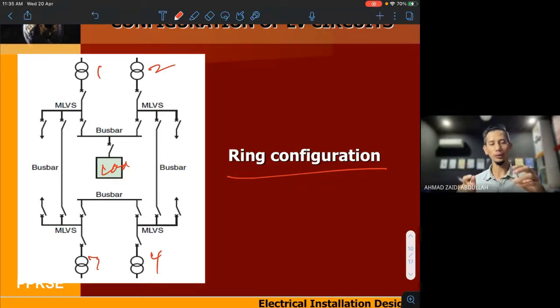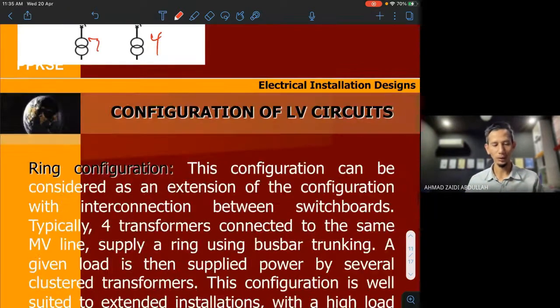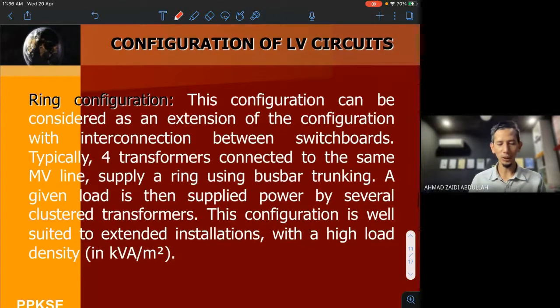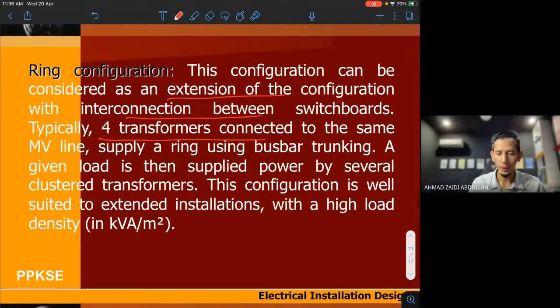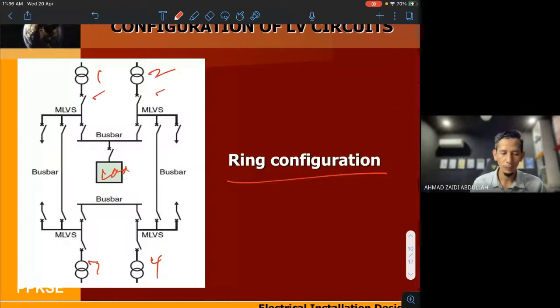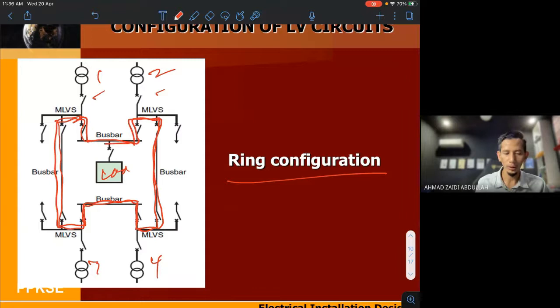If let's say this supply trips, you still have 3 supplies to back up your system. Okay, so this configuration can be considered an extension of the previous configuration, the interconnection. In the interconnection you only have 2, right? But for this ring you have 4 transformer supplies in a ring using bus bar trunking. So this one we call the bus bar. Okay, you see it is a closed loop, that's why we call it a ring.